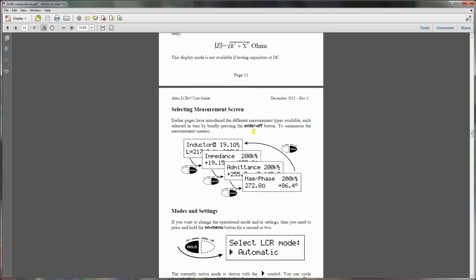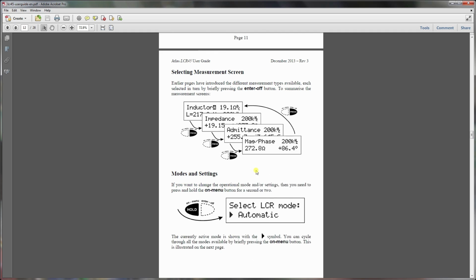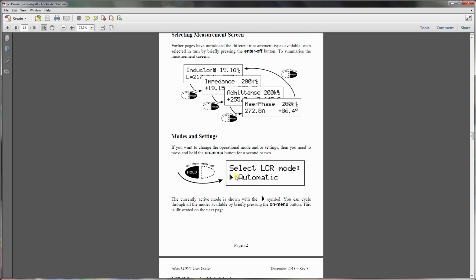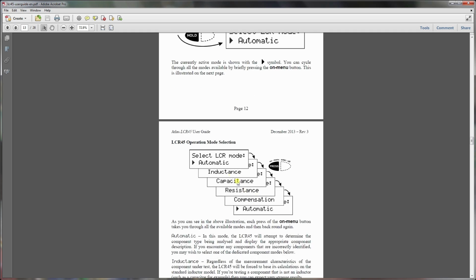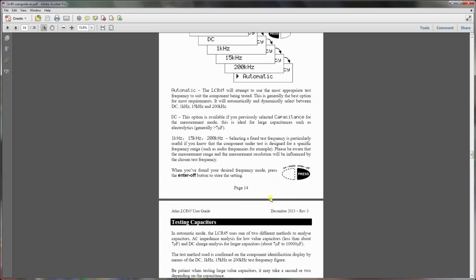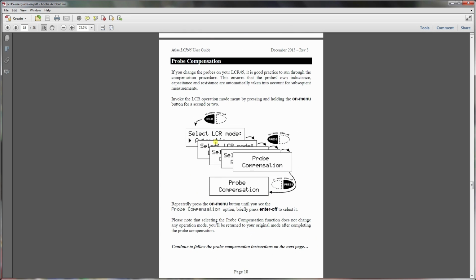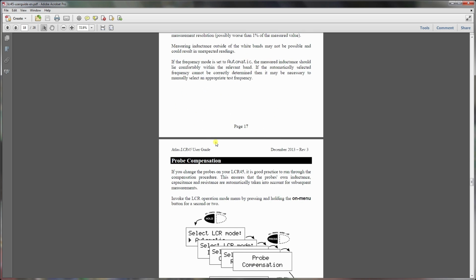And then you have the various measurement screens which you can scroll through, which we did earlier. You can also change the LCR from the fully automatic mode into manual mode, so you can switch it to inductance, capacitance, resistance if the LCR meter is getting confused with the component that you're measuring. And then you'll see there's also compensation here. So if we scroll through the manual, you'll see that you can do probe compensation to remove any of the artifacts that the probes may introduce into the readings.